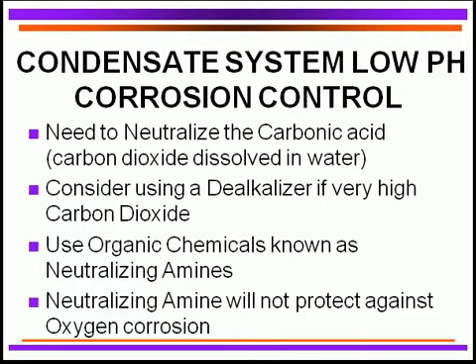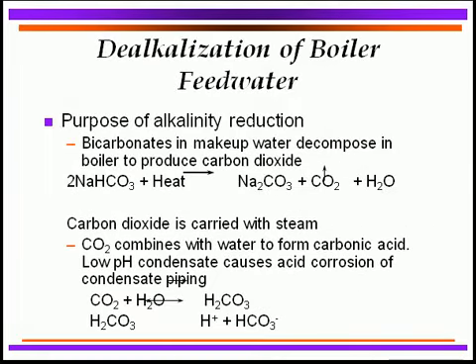Neutralizing amines will not protect against oxygen corrosion, so you have to consider what to do if you have oxygen corrosion. Regarding dealkalization of boiler feed water: the alkalinity in the makeup water — bicarbonate and carbonate alkalinity — is destroyed by heat and produces carbon dioxide. When that goes over with the steam and starts condensing, the carbon dioxide dissolves in the condensate, drops the pH, and makes it very aggressive.